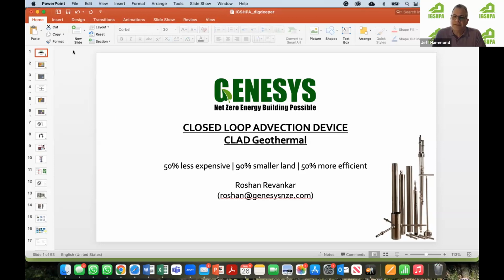If the heat of extraction is 3.5 tons, can it provide the 7-ton plus needed for a 6-ton cooling load? So 6-ton is nominal in cooling mode for a 56-degree groundwater temperature. As you can imagine, you have a lot more delta to play around with in the cooling mode. So that's why its capacity is greater.